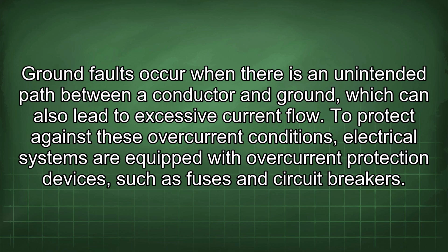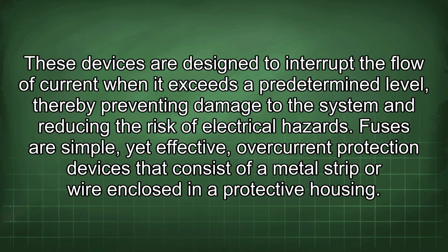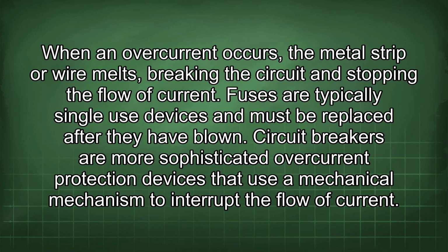To protect against these overcurrent conditions, electrical systems are equipped with overcurrent protection devices such as fuses and circuit breakers. These devices are designed to interrupt the flow of current when it exceeds a predetermined level, thereby preventing damage to the system and reducing the risk of electrical hazards. Fuses are simple, yet effective, overcurrent protection devices that consist of a metal strip or wire enclosed in a protective housing. When an overcurrent occurs, the metal strip or wire melts, breaking the circuit and stopping the flow of current. Fuses are typically single-use devices and must be replaced after they have blown.